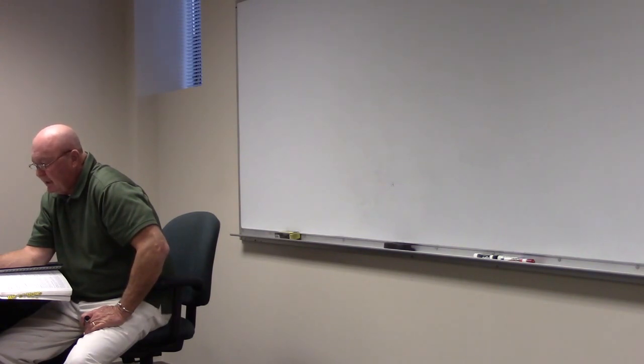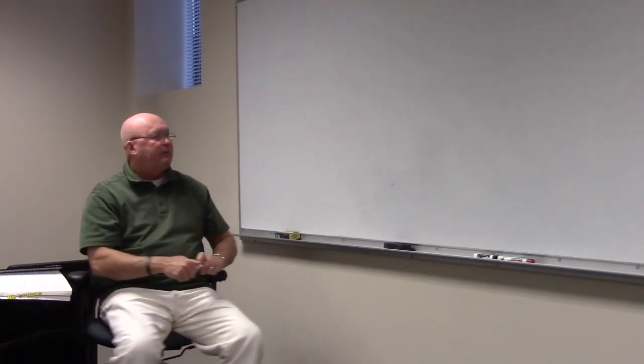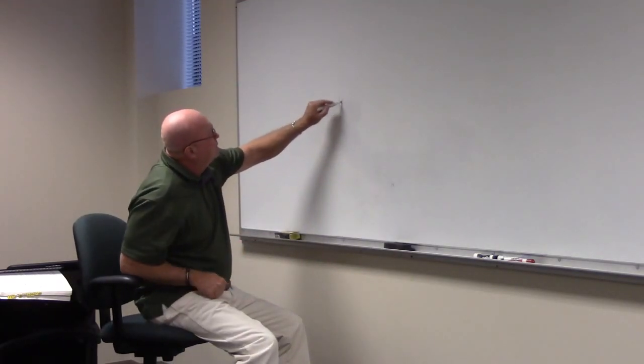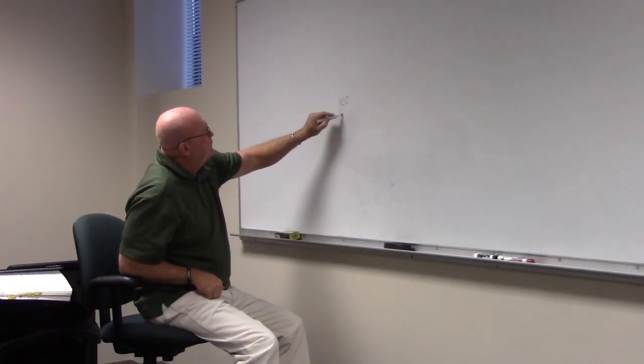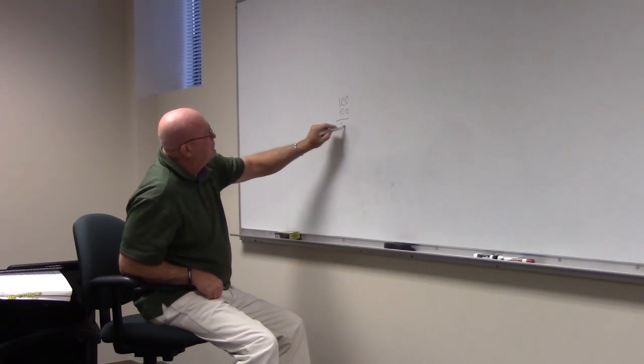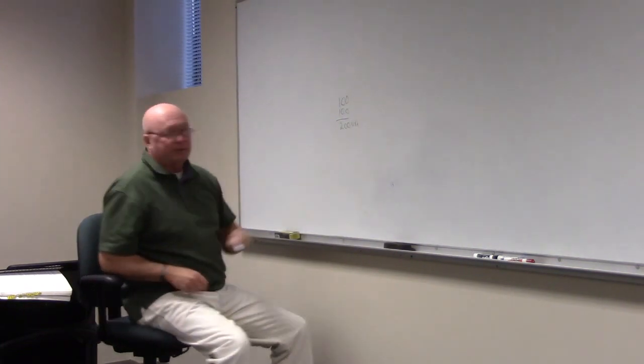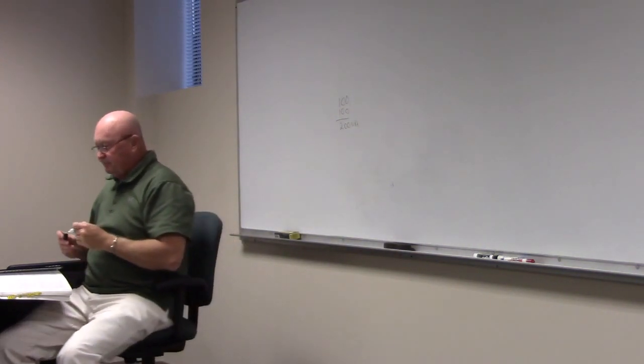2 fluorescent lights used to illuminate a 9x12. Since each contains 2 40-watt lamps, the ballast is rated 0.83 amps, which translates to approximately 100 VA. The total connected load for each fixture is 100 VA, and so for both light fixtures we get 100 plus 100, and we get a total of 200 VA for the lights. Okay.